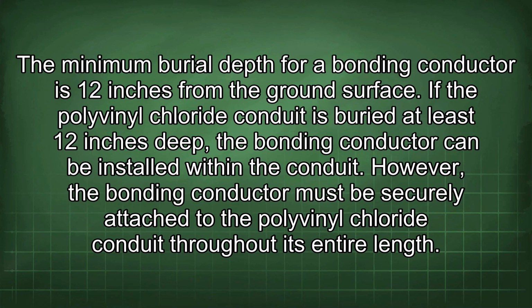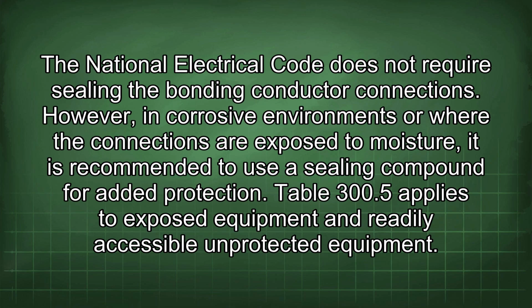The minimum burial depth for a bonding conductor is 12 inches from the ground surface. If the polyvinyl chloride conduit is buried at least 12 inches deep, the bonding conductor can be installed within the conduit. However, the bonding conductor must be securely attached to the polyvinyl chloride conduit throughout its entire length. The National Electrical Code does not require sealing the bonding conductor connections.